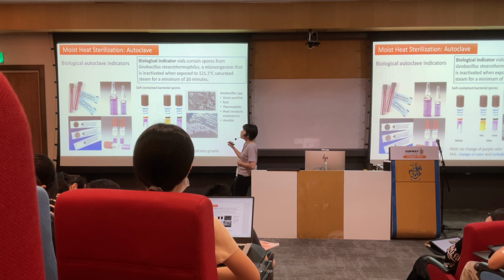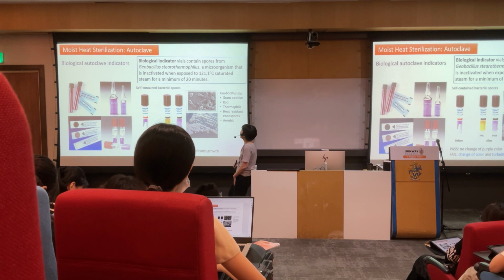The yellow is also a pH indicator. When it is acidic, it's yellow. And acidic is because the bacteria produce acidic product. And also you see the turbidity. There are two things you will see from the tube: color change and also turbidity. There's something wrong, indicating you failed to kill all the spores inside the autoclave. However, this way is more expensive. Buying this, I'd rather use the tape.